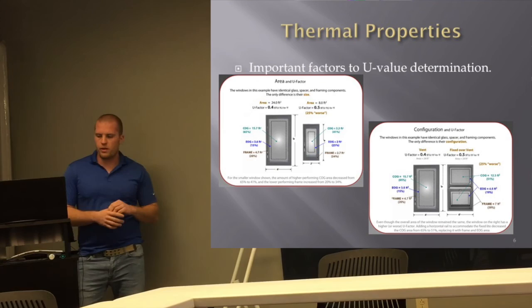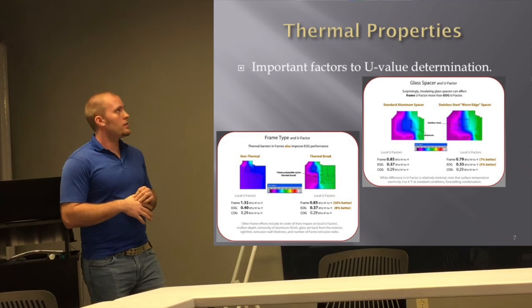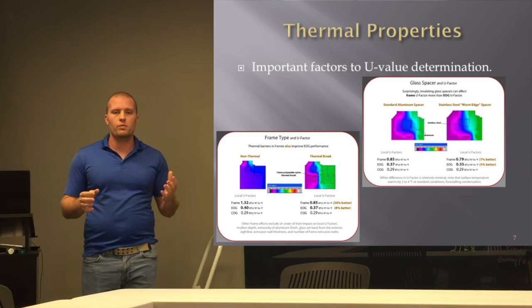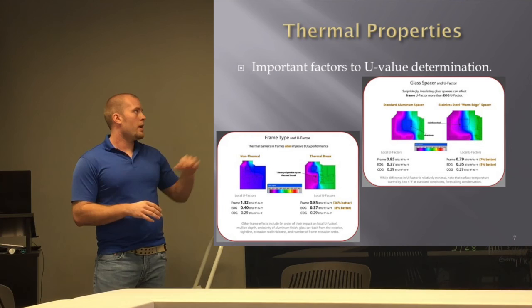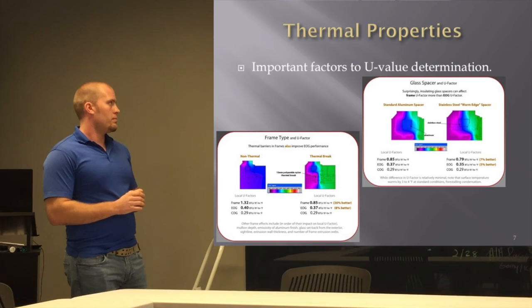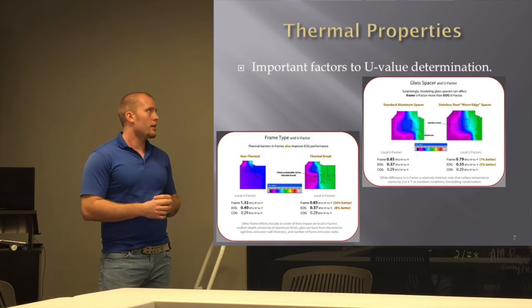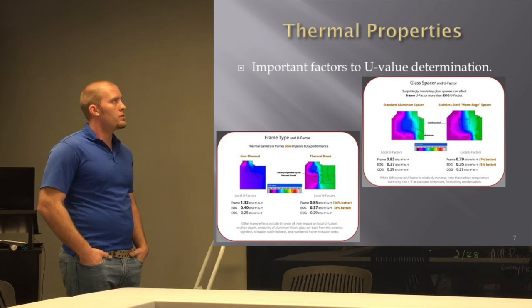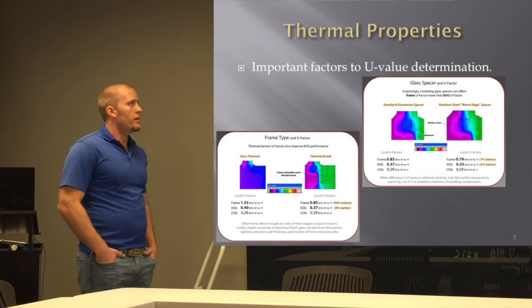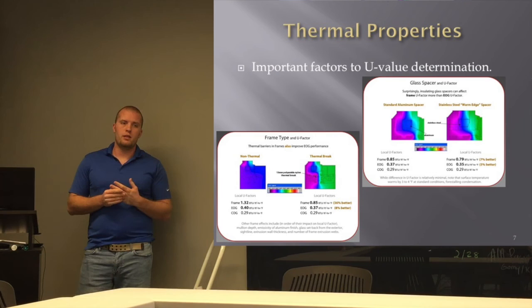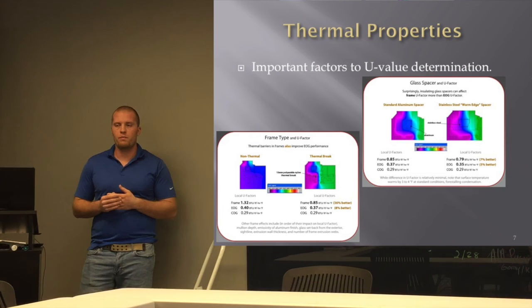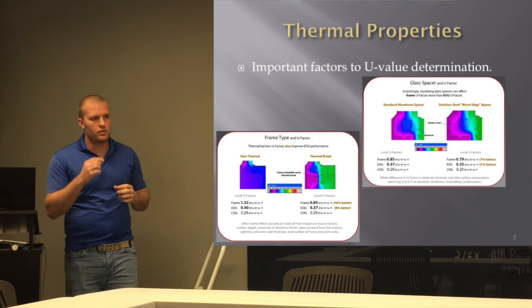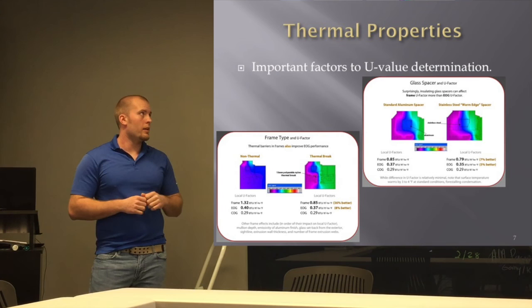Looking at frame and edge-of-glass performance: a non-thermal system has a frame U-factor of 1.32, which is quite high. A system with a thermal break — like a storefront system — is 36% better, dropping to 0.85. A warm-edge spacer using stainless steel instead of aluminum gives about a 7% improvement in U-factor. There's also a foam spacer product emerging, though architects don't love it because it creates a big black line around the window.